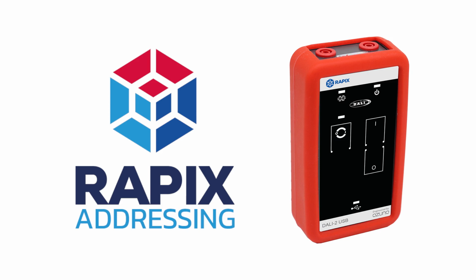If you're not familiar with what a DALI scene is, it's probably easiest to explain it with an example. Whereas a DALI group is used to issue the same command to multiple DALI devices at the same time, like turn them on or off or dim them up and down, a DALI scene is similar in that it's designed to command multiple DALI devices, but rather than setting them all the same command, it instead tells them all to go to a predetermined setting chosen for that scene.